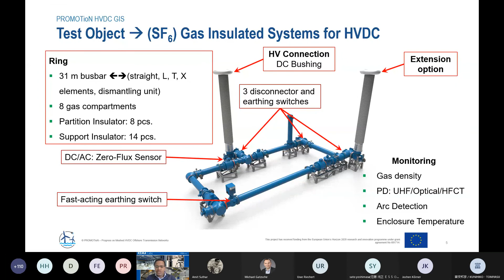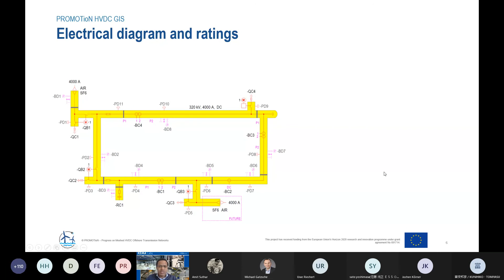Well, just to give you a highlight, the single line diagram of that GIS you just saw looks like this, with all the disconnectors and all the components. The nominal voltage of the HVDC GIS is 320 kV, and we have a continuous rated voltage of 350 kV. And of course, it has been specified what lightning impulse voltage we apply and what switching voltage we apply. I think Michael will give you the background on how it was specified and where it is coming from. And we have applied not only the impulse itself, but also superimposed impulse on top of the DC voltage.